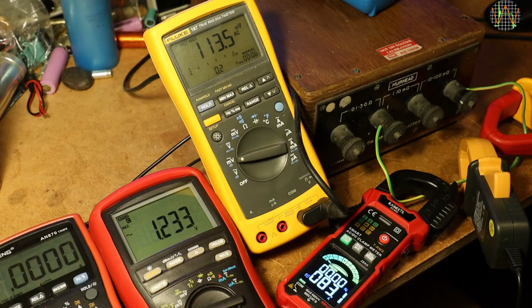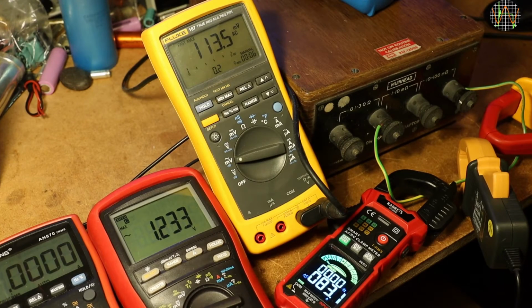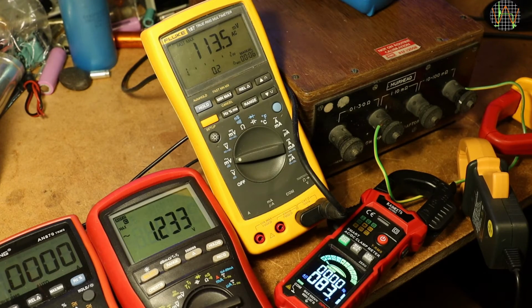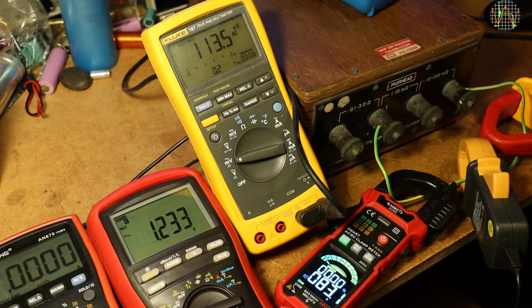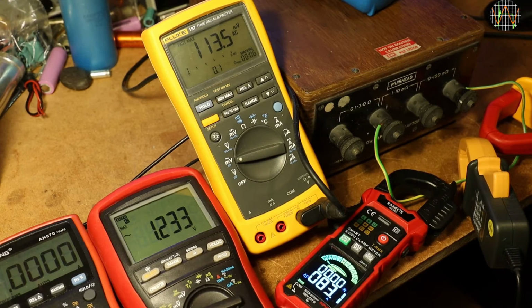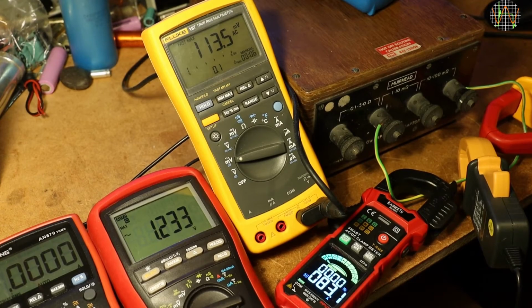The KC602 manual doesn't state how fast inrush is, but we can conclude it's slower than 1 millisecond. I looked at other comparable clamp meter specs, and it seems that the inrush function works more in the 100 millisecond range. My setup doesn't produce that kind of slower inrush, so I think it's fine that the KC602 is not capturing the ultra-fast inrush here and showing the typical max value instead.